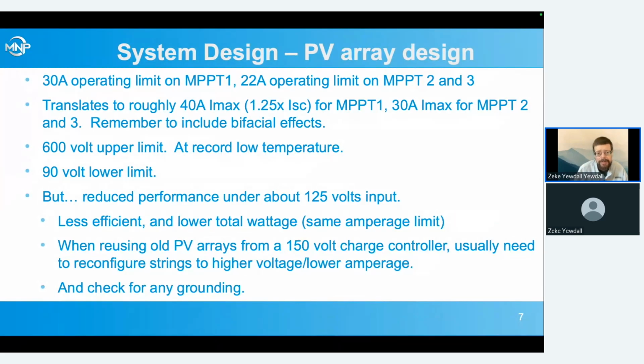Another thing to think about on system design is your PV array design. We've got a 30 amp operating limit on the first MPPT and 22 amps on the second and third ones. This translates into roughly 40 amps for maximum current, which is defined in the code as 1.25 times Isc of the PV array, and on 2 and 3, a 30 amp.